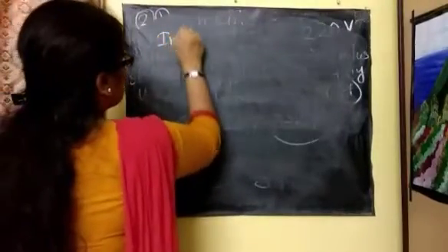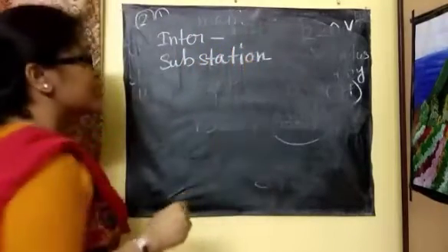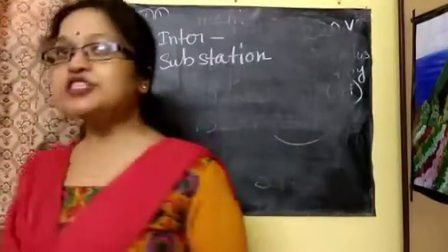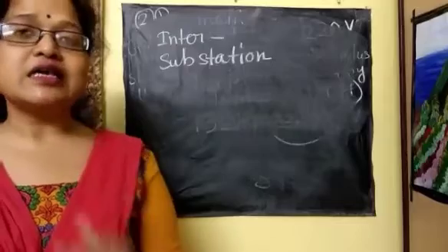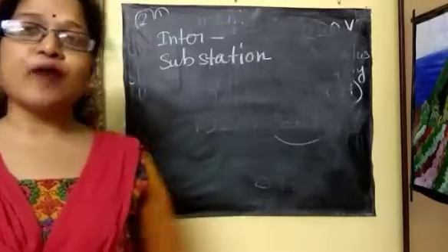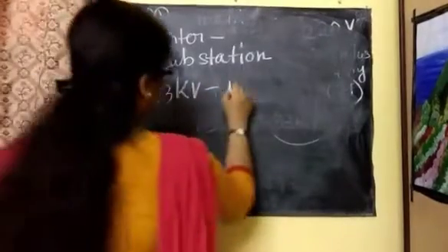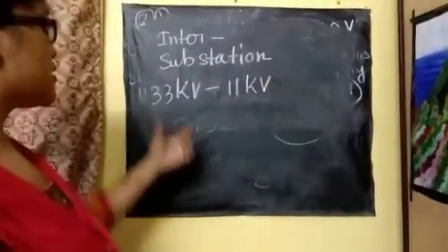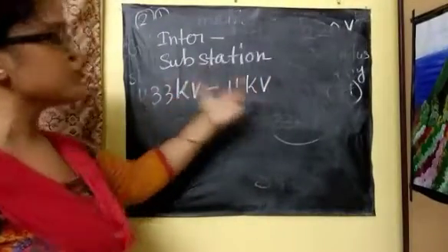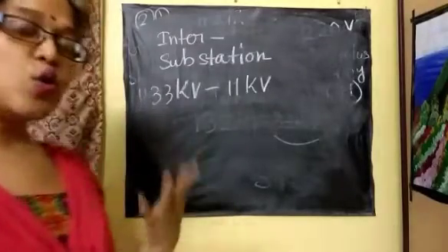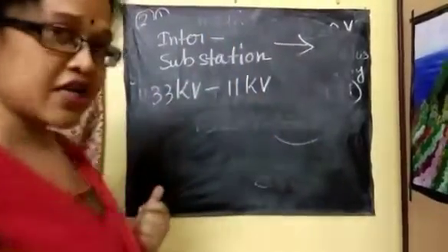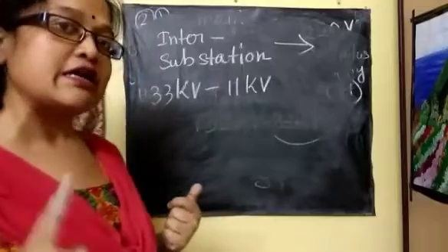The intermediate substation is the fourth part of this process. In the intermediate substation, there are a series of step-down transformers that convert 33 kilo volt to nearly 11 kilo volt. Light industries that need around 11 kilo volt of energy receive their power directly from the intermediate substation, not from the main substation.